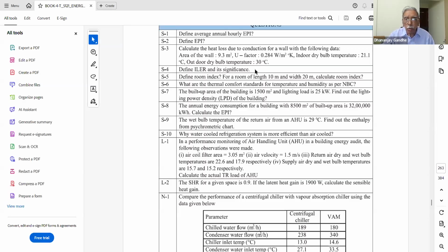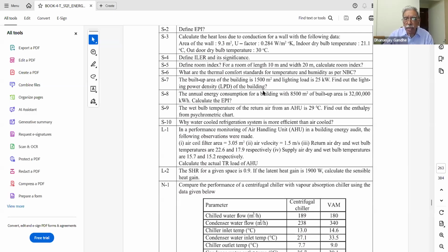ILER is basically the installed load efficacy ratio. This installed load efficacy ratio is the ratio of actual lux, expressed in lux per watt per m square. That is the actual illumination figure. And the design figure is the target lux illumination level per watt per m square. So the ratio of the two is the installed load efficacy ratio. Do you get me? Yes, sir, I got it.